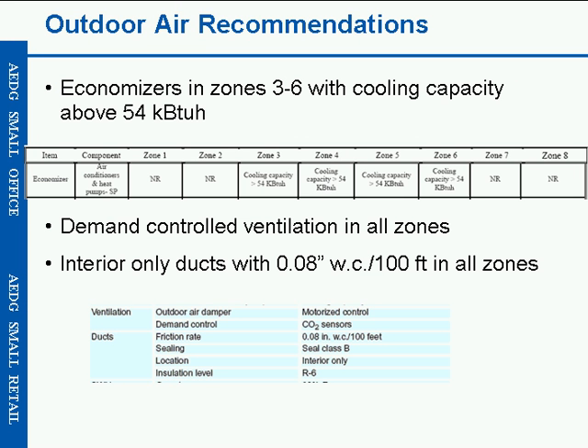Some of the additional pieces of the HVAC design focus on economizers. Economizers are recommended for both the small office and small retail design guide in climate zones 3 through 6, for systems greater than 54,000 BTUs per hour. This is a slightly smaller system size than code requires, and economizers are not recommended in climate zones 1, 2, and then 7 and 8.